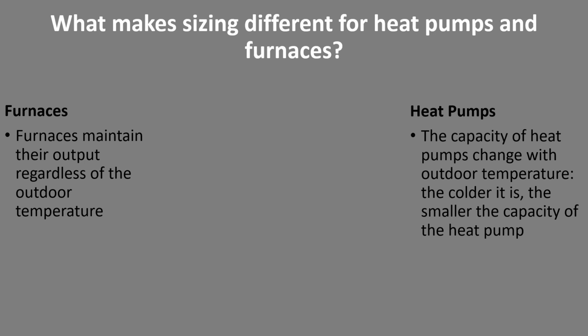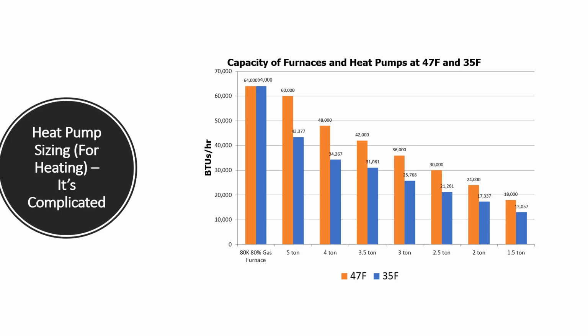What makes sizing for heat pumps different from furnaces? Furnaces, they maintain their output regardless of the outdoor temperature. Most heat pumps, the capacity of the heat pump changes with outdoor temperature. The colder it is, the smaller the capacity. This chart indicates what we said on the previous slide. And here we have an 80K, 80% gas furnace. And sure enough, whether it's 47 degrees or 35 degrees outside, the capacity is the same.